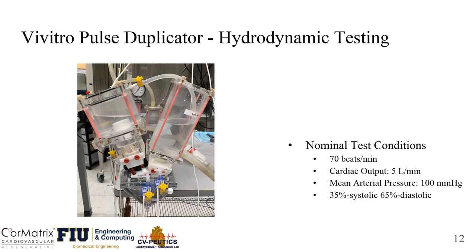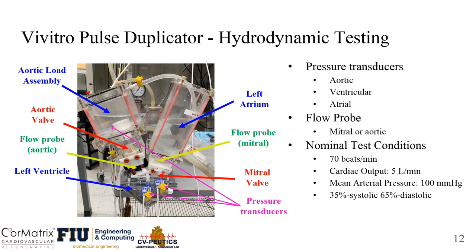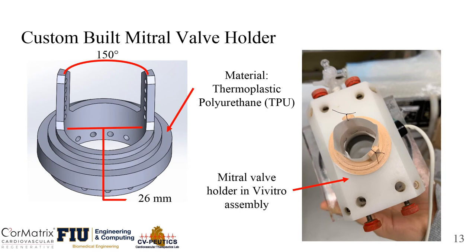To proceed with hydrodynamic testing, we are using a Vivitro pulse duplicator device. It is a system that simulates the left side of the heart and consists of a ventricular chamber, atrium, and aortic load assembly. The system allows placement of aortic and mitral valves. Three pressure transducers are placed in the aortic, ventricular, and atrial positions, and a flow probe is attached in either the mitral or aortic location. To secure the valve in the Vivitro system, we 3D printed a valve holder using TPU. The valve is sutured around the annulus in two posts at 150 degrees apart to simulate the anterior and posterior leaflets.